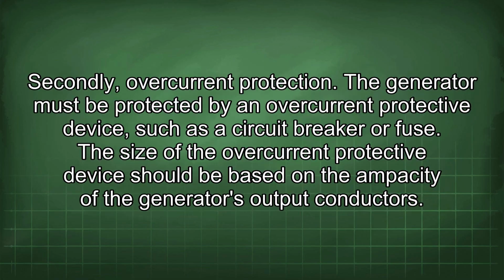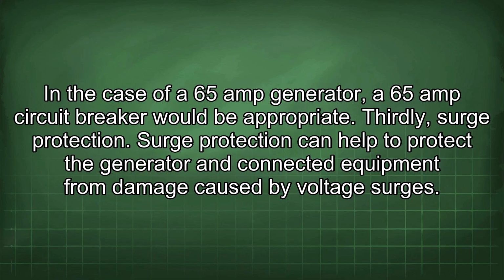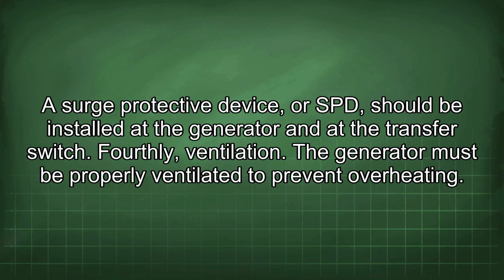or water pipe. Secondly, overcurrent protection. The generator must be protected by an overcurrent protective device, such as a circuit breaker or fuse. The size of the overcurrent protective device should be based on the ampacity of the generator's output conductors. In the case of a 65 amp generator, a 65 amp circuit breaker would be appropriate. Thirdly, surge protection. Surge protection can help to protect the generator and connected equipment from damage caused by voltage surges. A surge protective device, or SPD, should be installed at the generator and at the transfer switch.